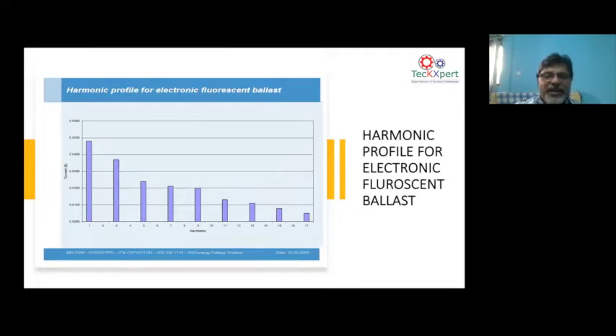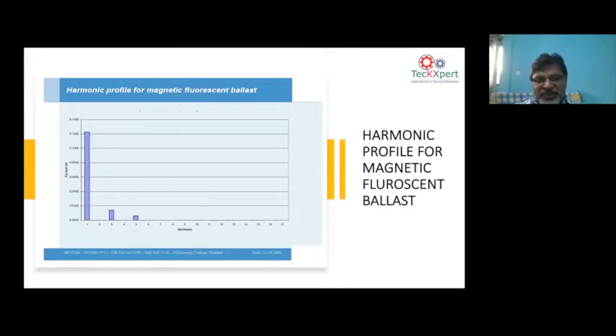Now going to the next, the next one is a magnetic ballast. A magnetic ballast has no electronics here, but even in a magnetic ballast, you will have some harmonics coming in. And many times it could be because of the saturation of the ballast itself. You see a third and fifth, a small level of harmonics, because if the little magnetic portion gets saturated, then you can have a certain amount of third harmonic flowing. Very small, so I won't categorize this as a harmonic producing load, but certainly it's a low power factor problem because magnetic ballasts all have a very low power factor. Go to the next.